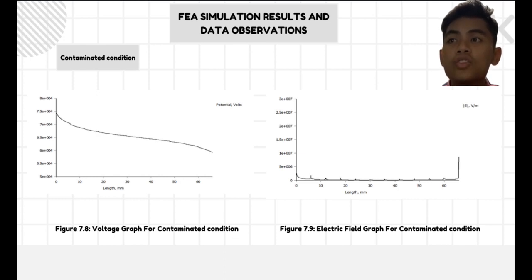The graph shows that the electric field starts dropping slowly at 2.5 MV per m, then gradually decreases before experiencing a sudden increase until reaching 7.5 MV per m at a 60 mm length. In contaminated condition, the presence of pollutant or conductive material on the surface of an insulator can create conductive paths. The conductive path allows current to flow through the insulator, resulting in leakage current. The presence of leakage current can lead to a decrease in the effective resistance of the insulator. When the effective resistance decreases, it means that the insulator becomes less effective at preventing the flow of current. This can result in an increase in current flowing through the insulator compared to when it is clean.